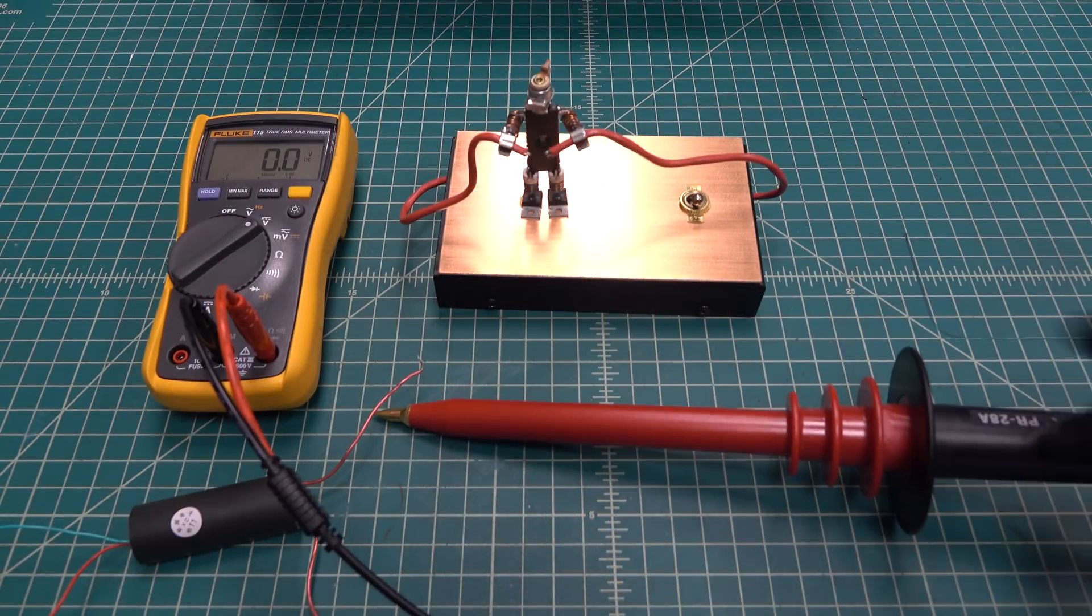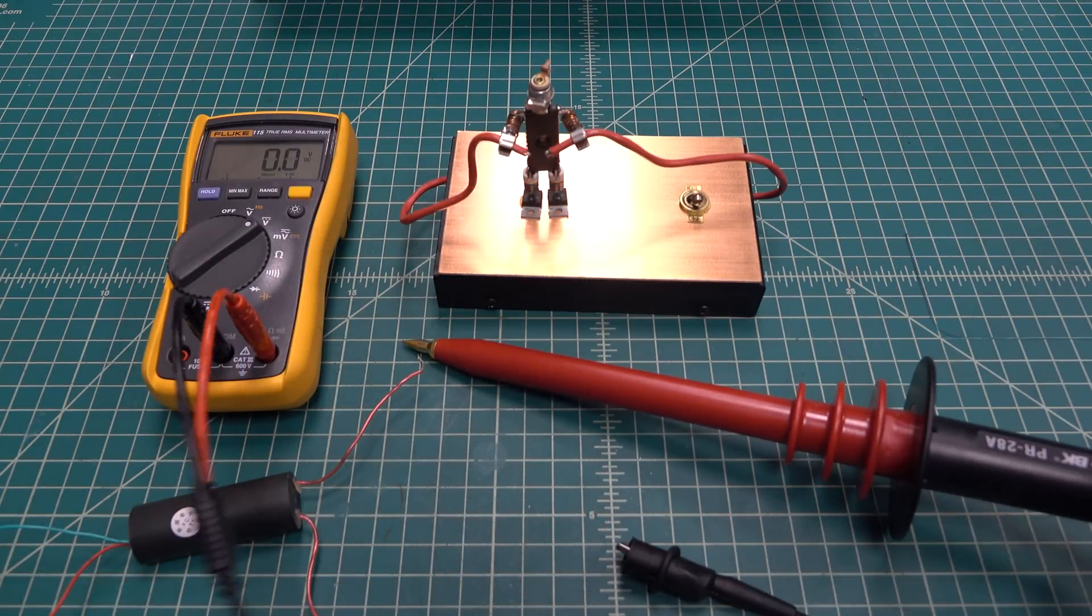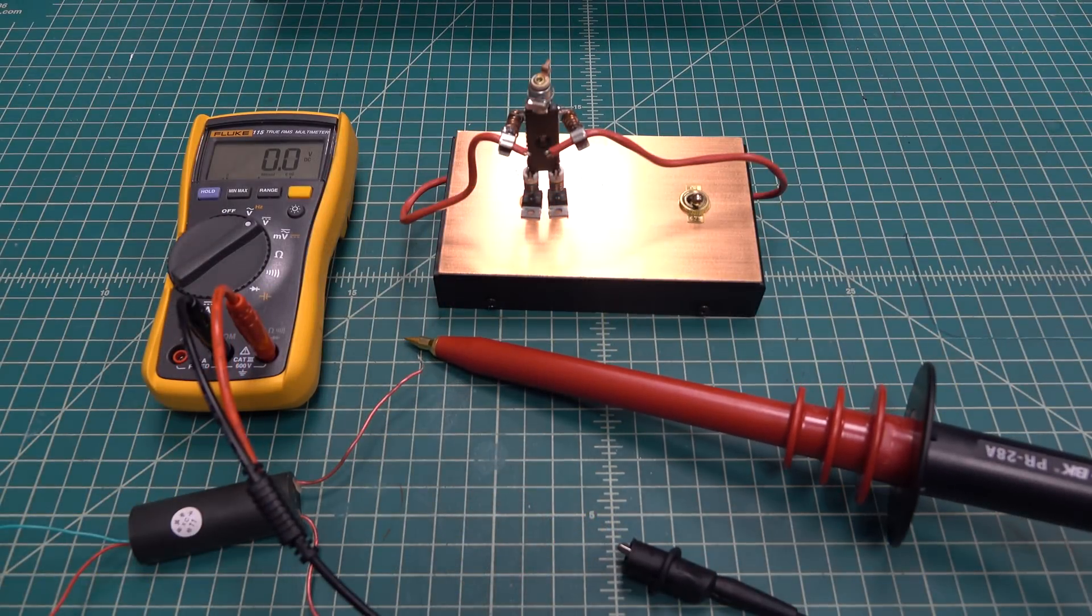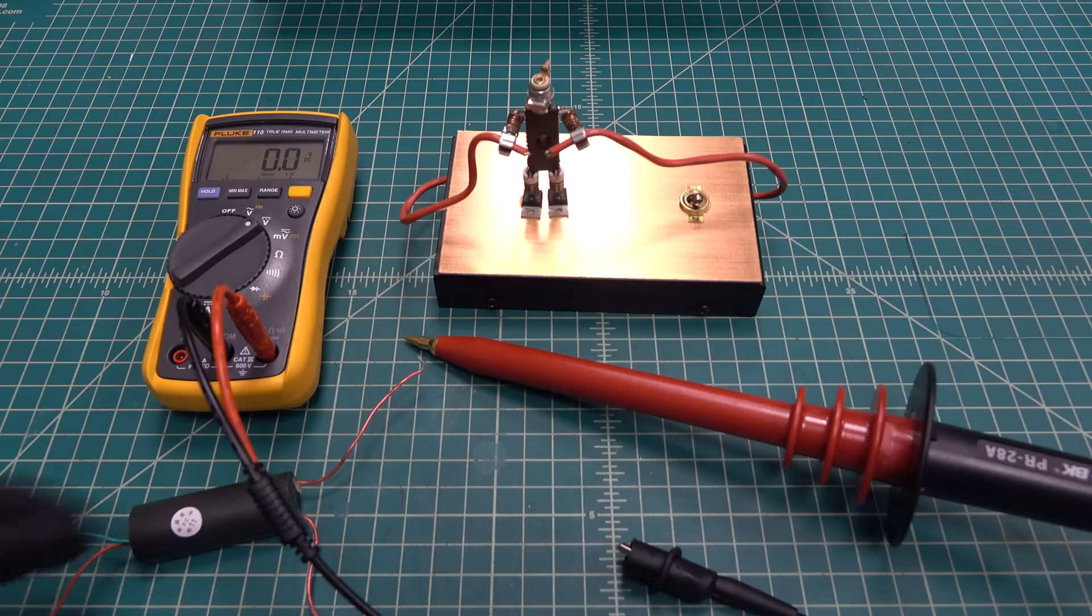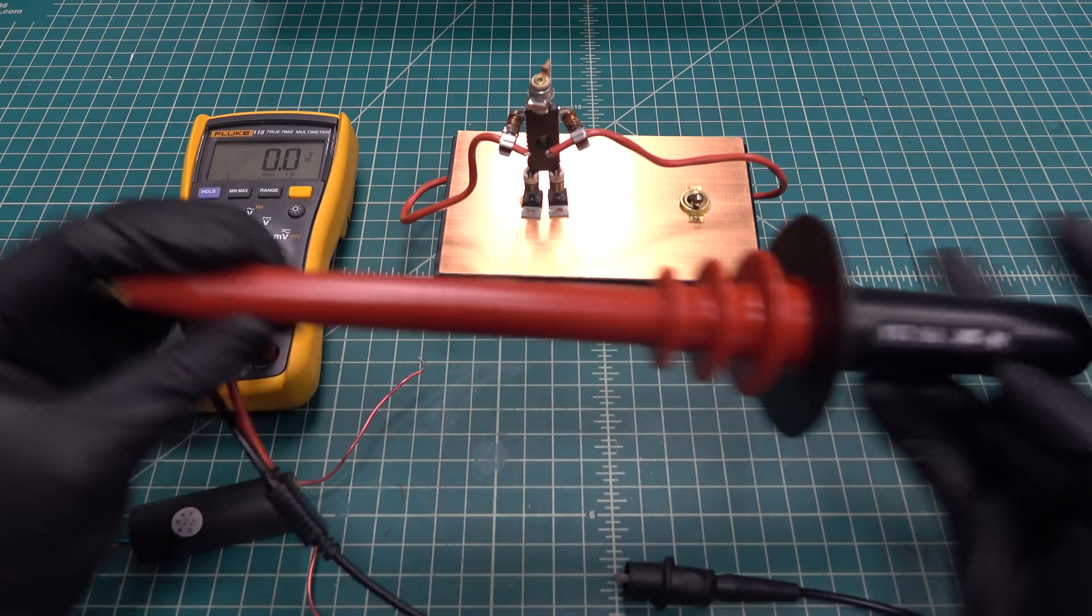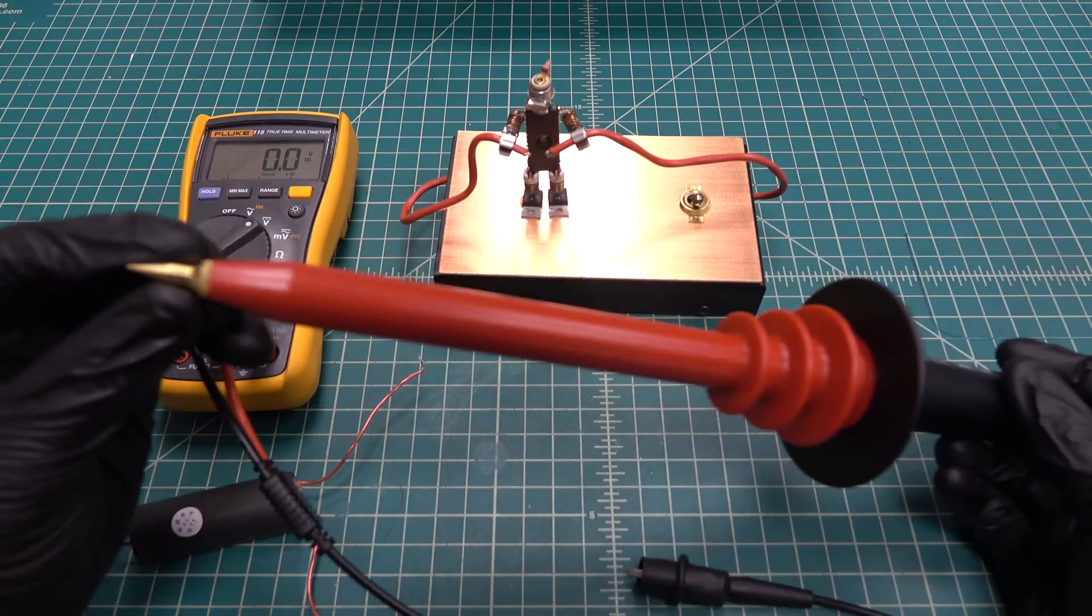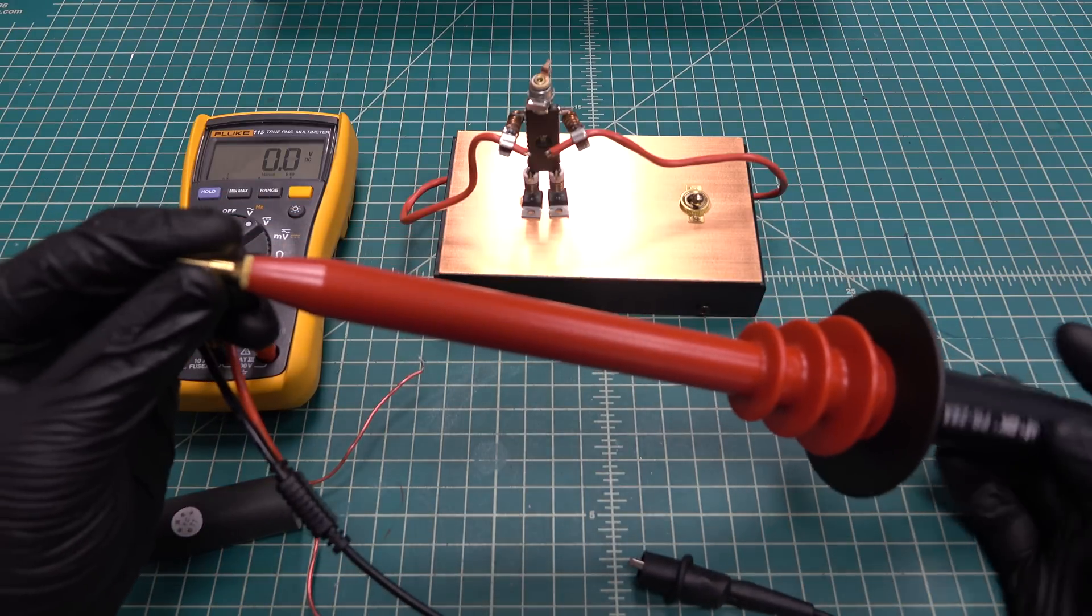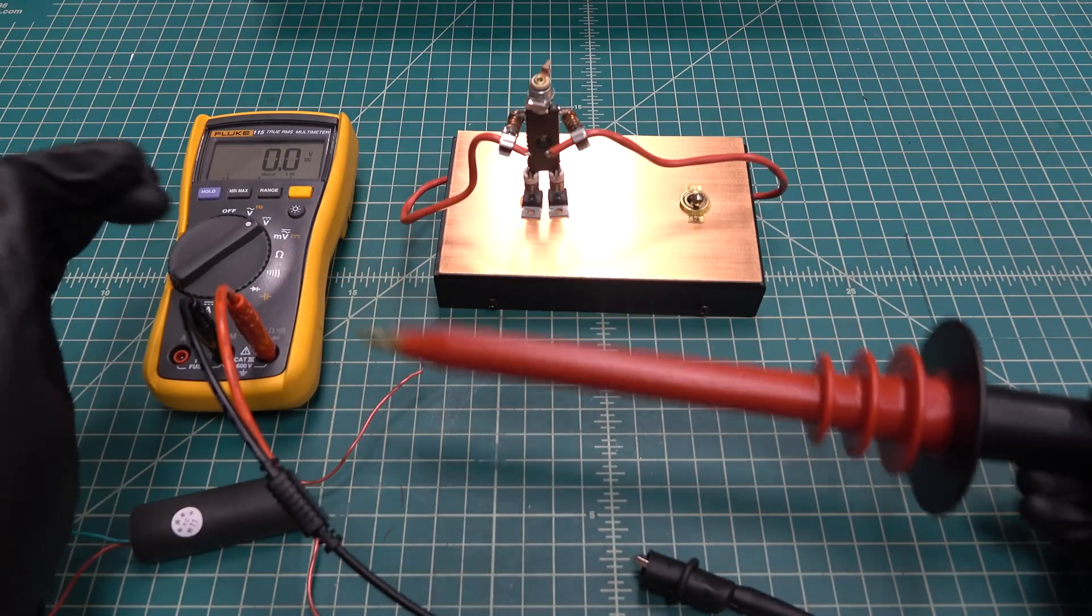If you ever need to measure voltages above 1000 volts, you're going to need to use a high voltage probe with your multimeter. It's essentially just a 1000 to 1 voltage divider, so for every 1000 volts the multimeter will register 1 volt.